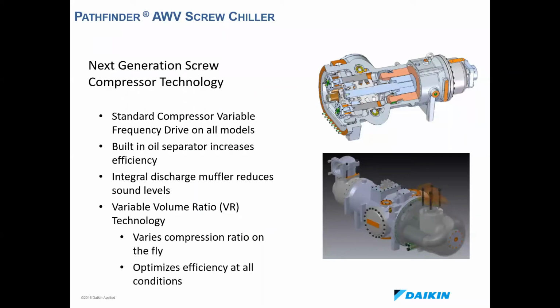So getting started on the VVR. What you've got here is a little compressor cutaway of our screw compressor. All of our screw products are going to have this VVR technology. That includes the water-cooled screw as well, WWV, but we'll stick to the AWV today. Before we get into VVR, there's a little note here talking about the IDCM I mentioned, the internal discharge compressor muffler. That is this right here. It's pretty much the oil separator. But this extra mass helps a lot with reducing the discharge sound, the sound of the discharge of the compressor. This also would improve the efficiency of the compressor as a whole, because it's internal to the compressor.